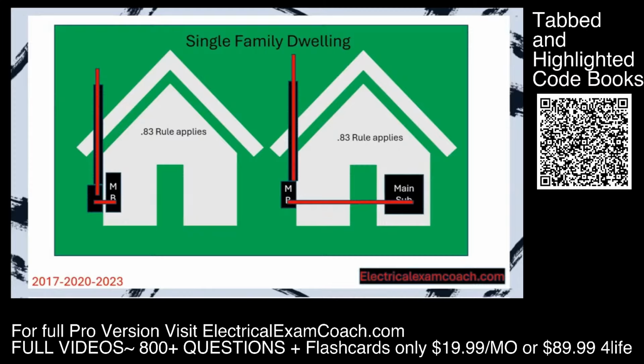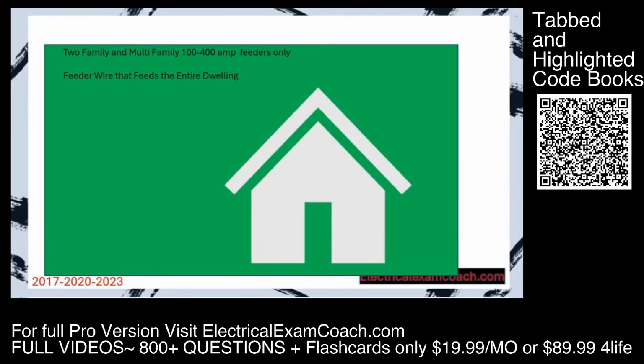You would go to that table, do your cheat sheet, find your size breaker, slide over, and you'd be able to use that size wire. Let's dive into two-family and multifamily. This is 100 through 400 amps, and this applies to the feeders only. The feeder must feed the entire dwelling.